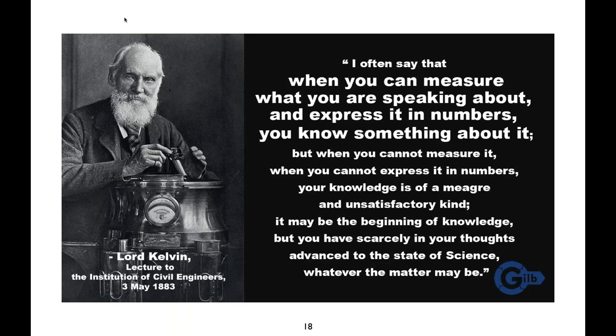Absolutely, it's a great question, and that really is at the core of this. I think when water was cheap and we didn't care, you'd have a manual valve and over time figure out how much you had to open it to keep the tubes from fouling. There was really no science, physics, or engineering behind it, just keep bleeding off water, kind of like I do with my evap cooler at home. But as time's gone on, and it's become more critical to manage this blowdown, we do it in different ways. Probably the most common is conductivity. You look at the electrical conductivity of the water stream, which correlates to the amount of calcium in the water, and indirectly, if the conductivity is at a certain level, that correlates to a dissolved solids value, and that's what we're controlling to.